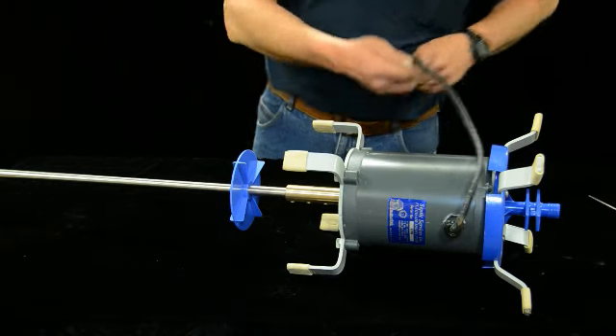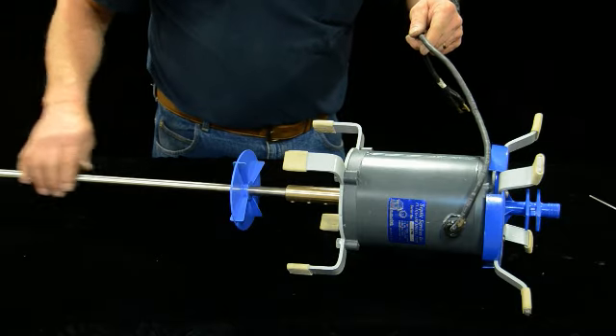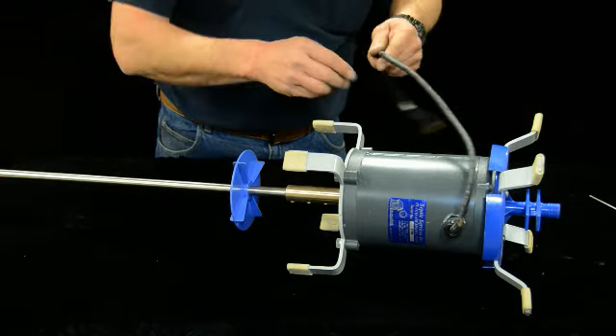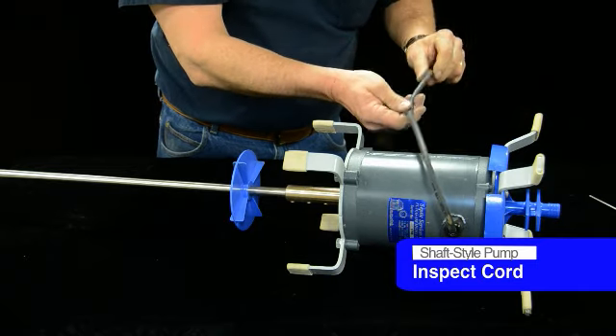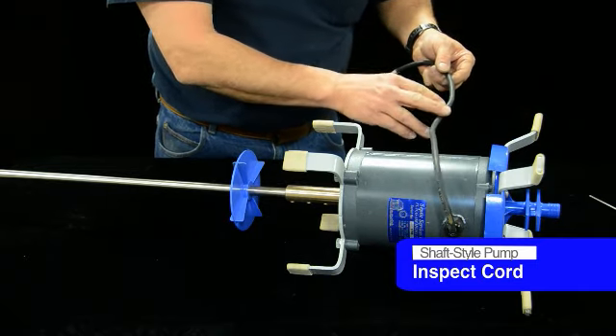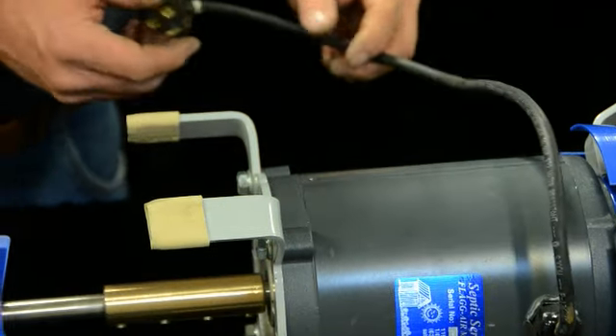The other thing you want to look for on the cord: if this thing's been vibrating around in there because there's been debris on it or the shaft is out of balance, quite frequently you'll see wear spots where there's a bare wire showing. You want to go ahead and replace that cord if you have a bare wire. Same way on the other end where you're plugging it in inside of the riser.